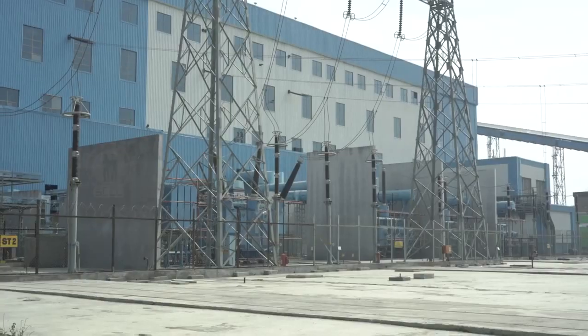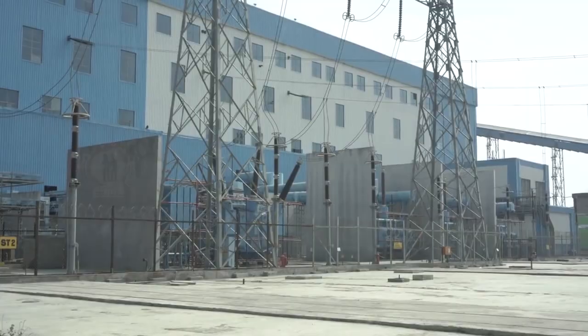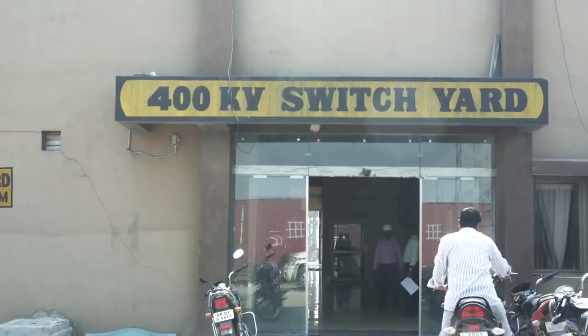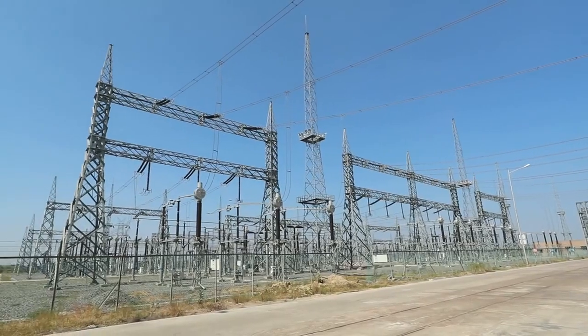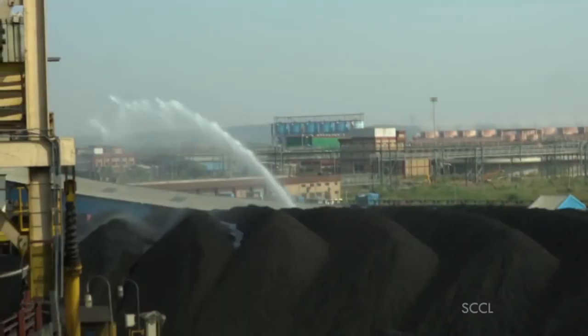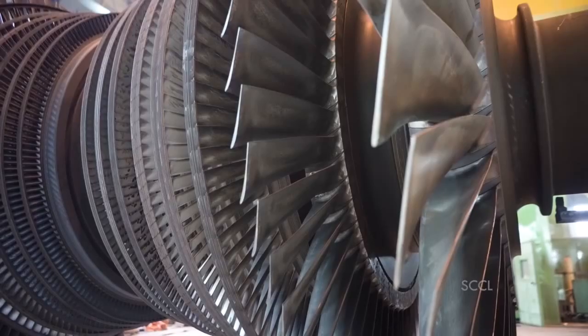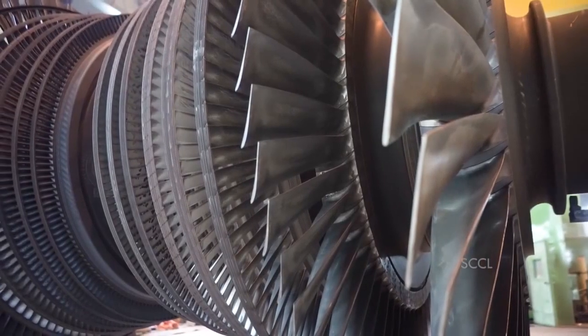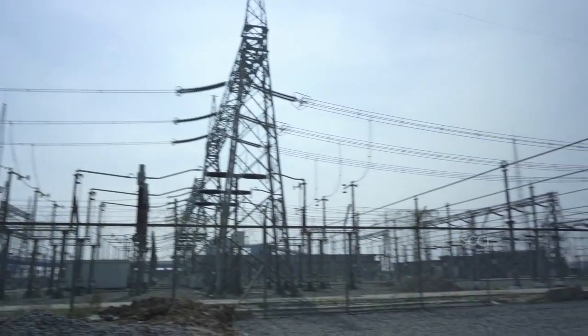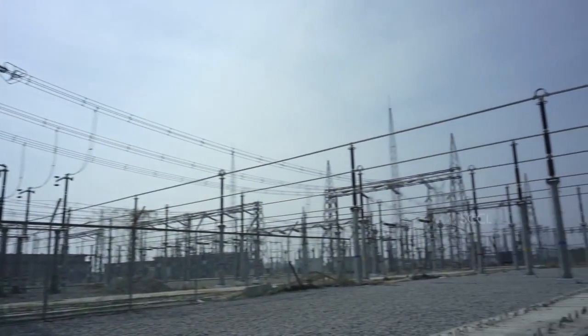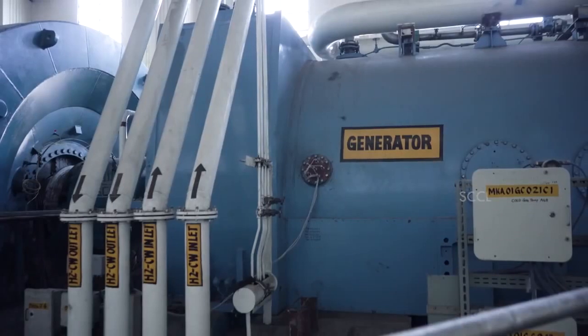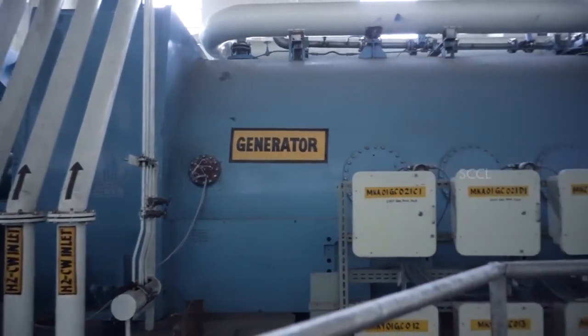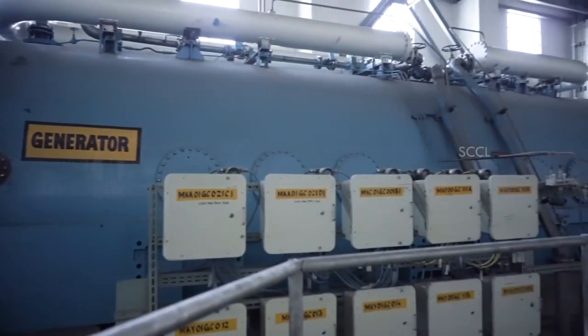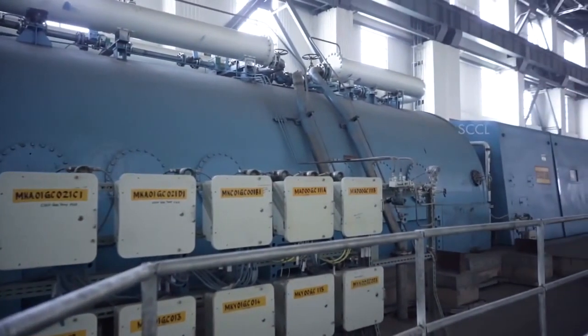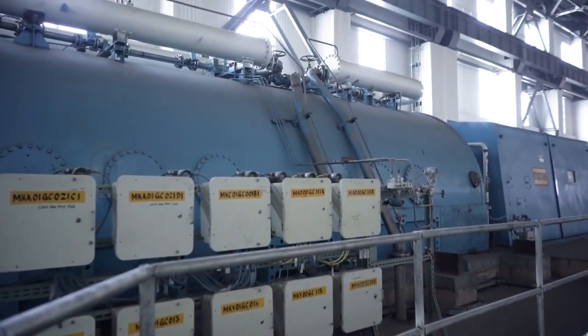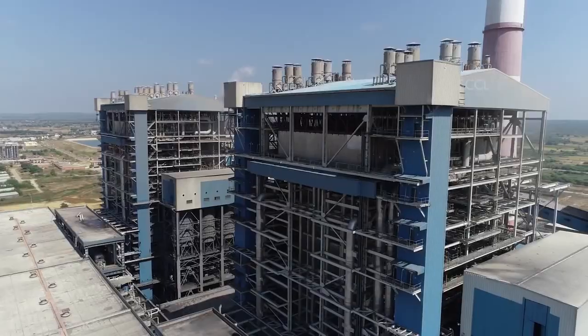Which is stepped up to 400 kV through transformers and is transmitted through 400 kV switchyard to the power grid. So, basically burning coal boils water to make steam and spin many tons of stainless steel to create thousands of volts of electricity. The generator continuously creates an electrical charge of 21 kV of electricity, which is equal to 600 megawatts, that is 6 lakh units per hour.